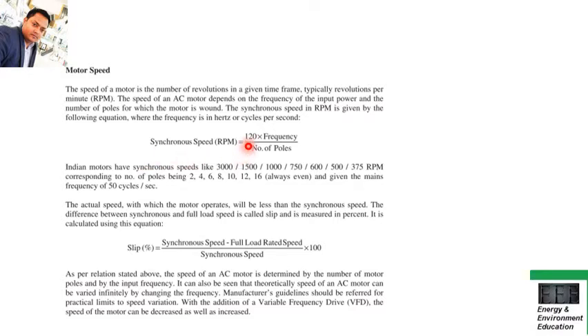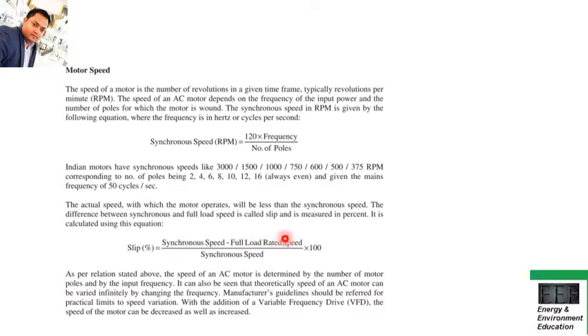The synchronous speed formula is 120 times f divided by P. Another important formula is slip percent: synchronous speed minus full load rated speed, divided by synchronous speed, multiplied by 100. They will give you the synchronous speed and full load rated speed and ask you to calculate slip percent — unless you remember this formula you will not be able to calculate it.